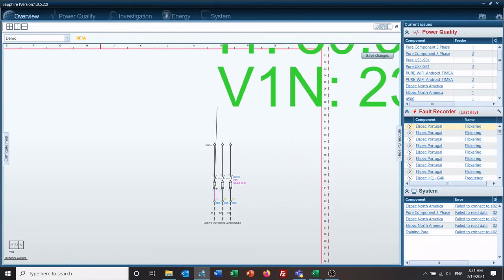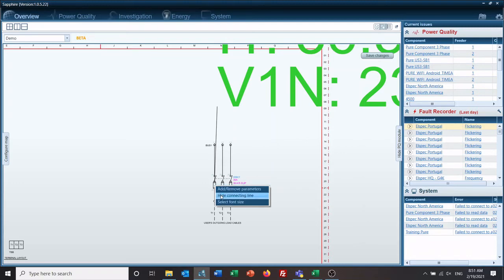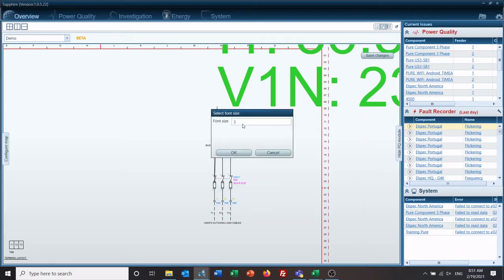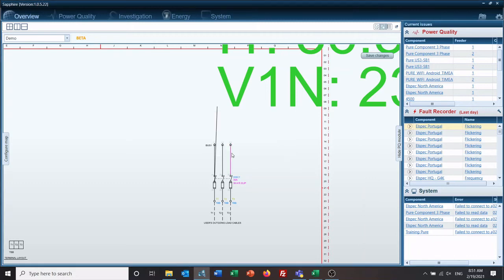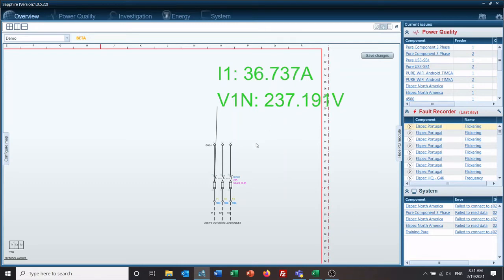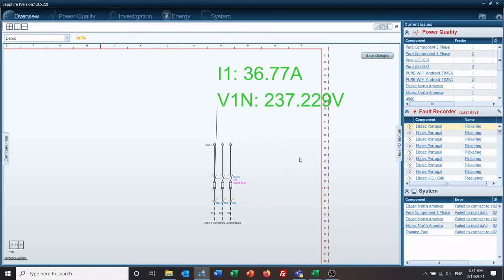To adjust the font, you go back to your object, right-click. Now you can add or remove parameters, hide the connecting line, or select font size. We're going to drop this down to one, which is the smallest you can go. So now I'm showing that I have 37 amps on phase one, 237 volts on phase one. I could add here and here, so I could actually see all my three-phase parameters in this one area.